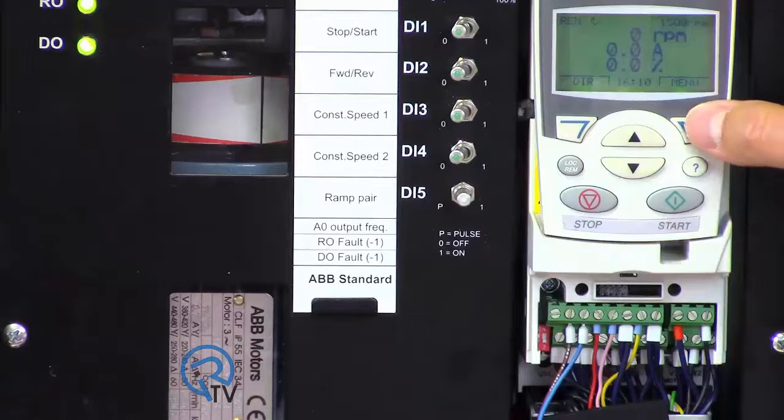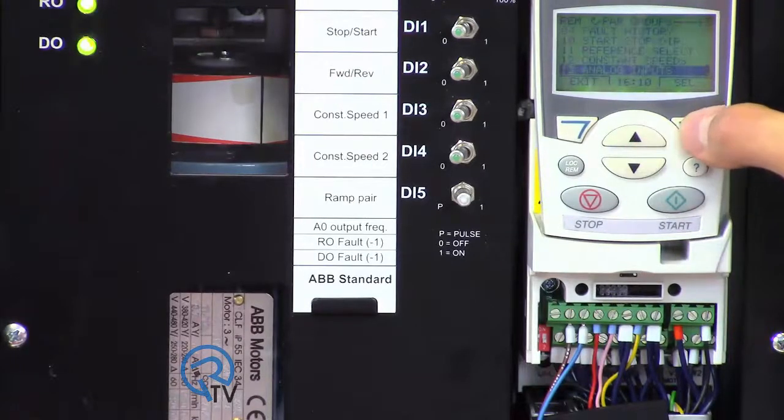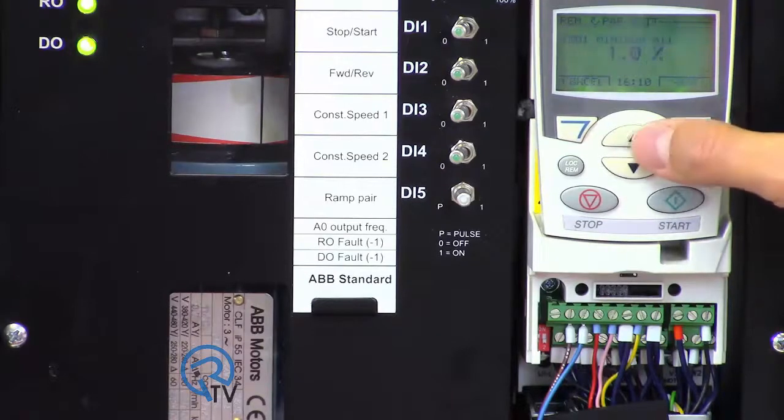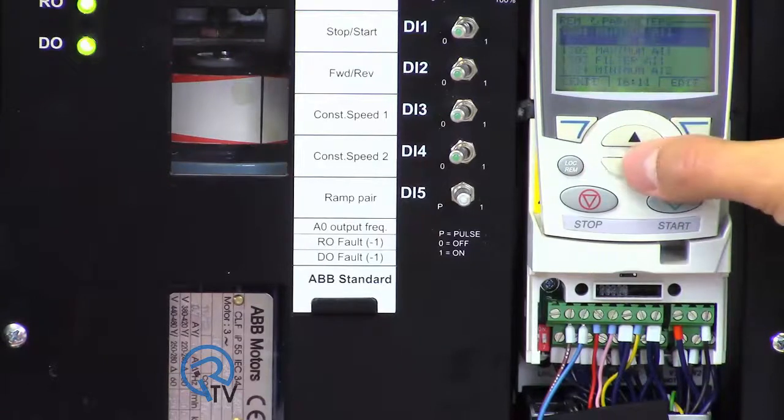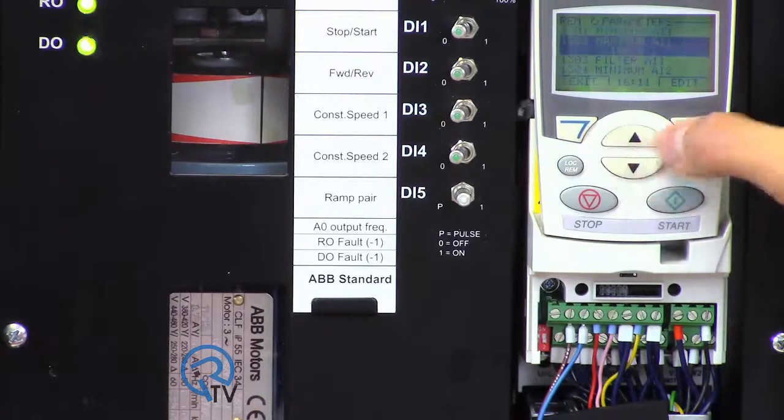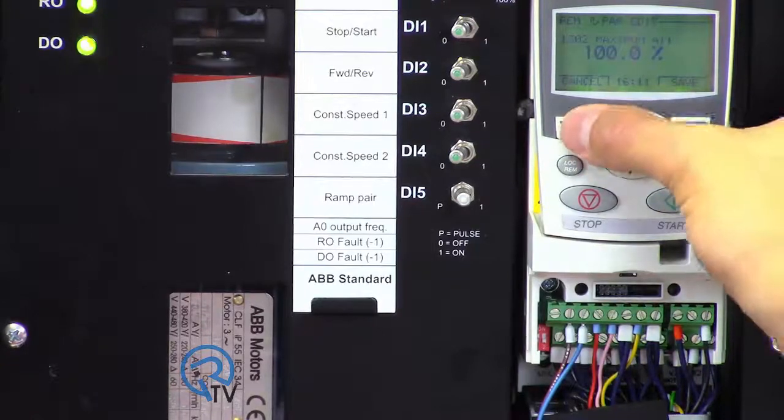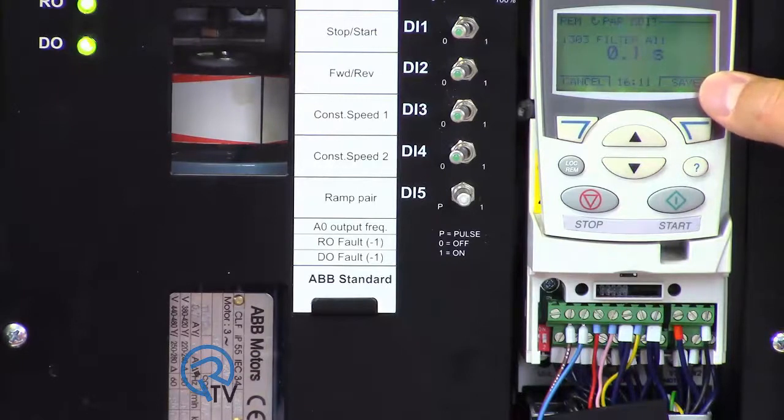Using the keypad, navigate to parameters, analog inputs, group 13. Our minimum input is 4 milliamps, so we set parameter 1301 to 20%. Our maximum input is 20 milliamps, so we leave parameter 1302 at 100%. If we wanted to filter out noise, we could do that with parameter 1303.